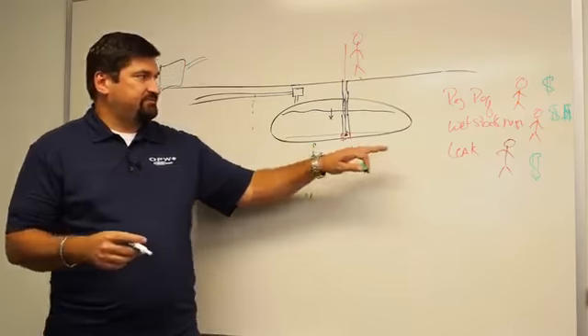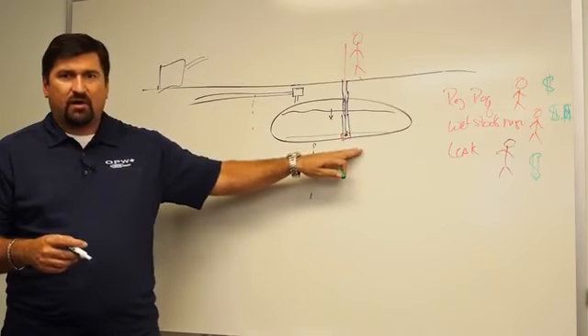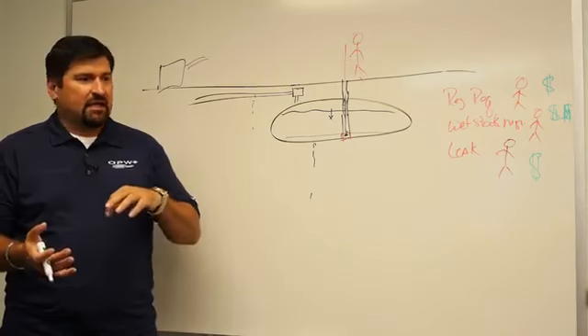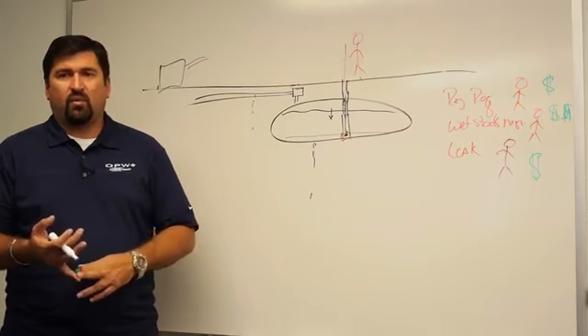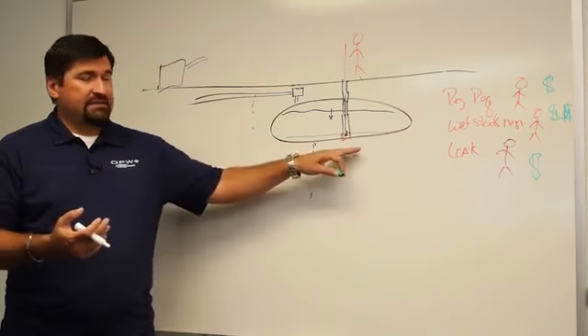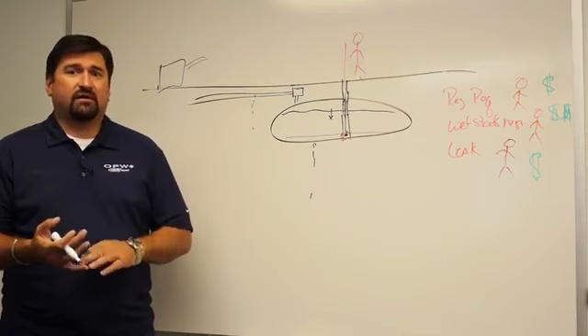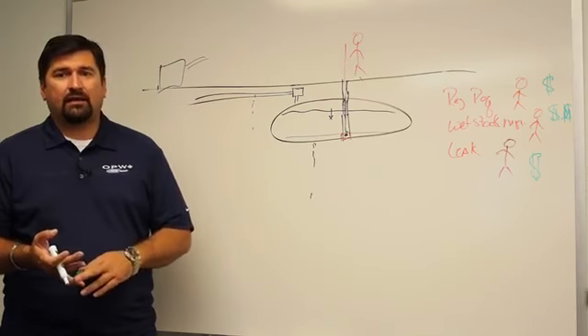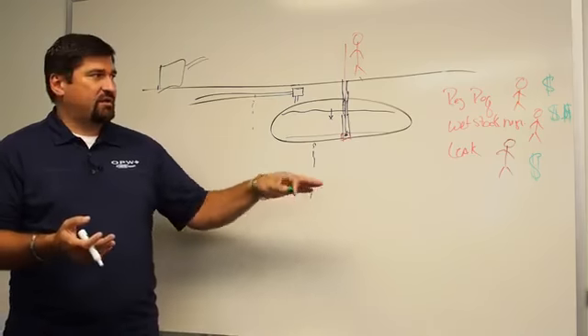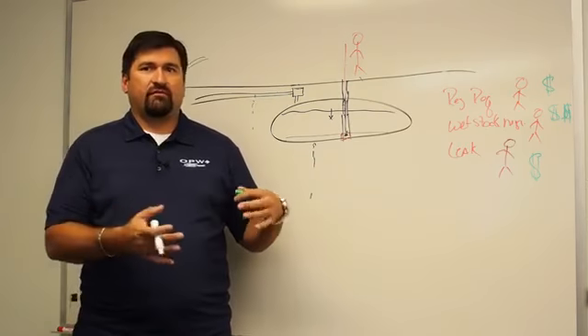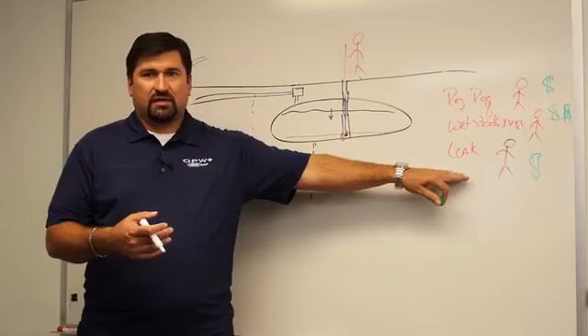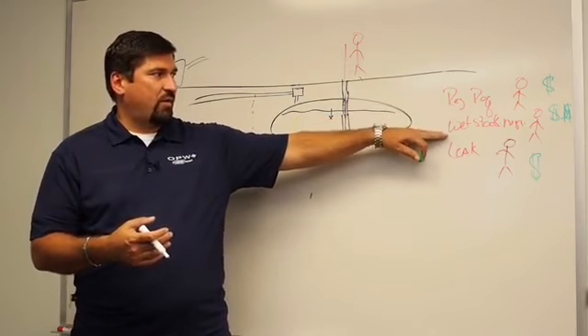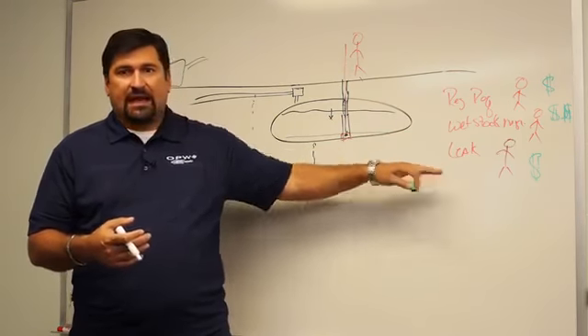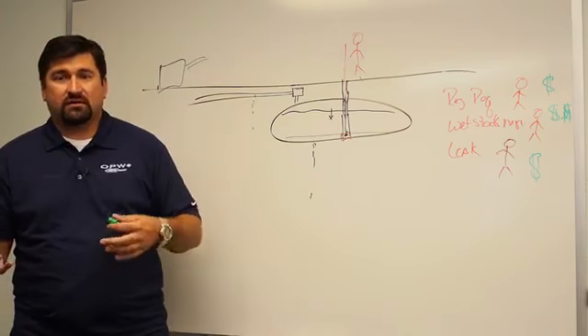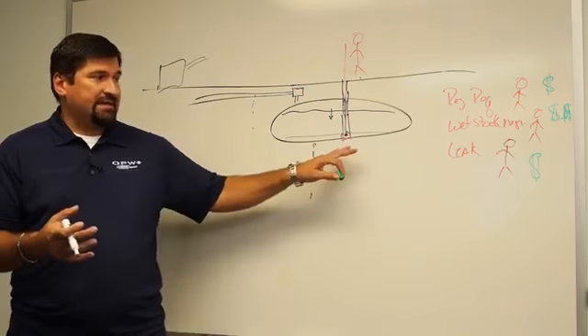But your leak test, this is where you're hiring a third party to come out and actually test the tanks, making sure that you're running either a 0.1 or a 0.2 test annually. And these can range anywhere between $150 to $350 per tank per line every year. So at the point in which you're looking for a return on investment, this is where you start looking at the return on investment, regulatory requirements, wet stock management, and actually doing the leak testing for that end user or that customer at that facility.